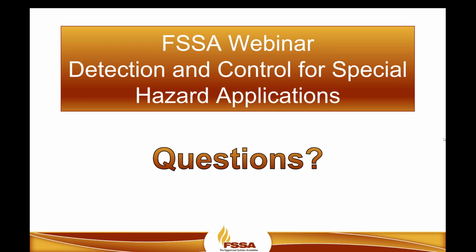Cool. So the next question is, required to be listed for use with the system? Absolutely. Control systems will have a list of the releasing devices that they went to UL, and that means that device is approved for the releasing from that control panel, whether it's a hard wire or it's a releasing module off of an addressable panel. Those devices, this is really pertinent in upgrades and swap outs of older systems. It's imperative to make sure that these devices are listed with what you're installing.